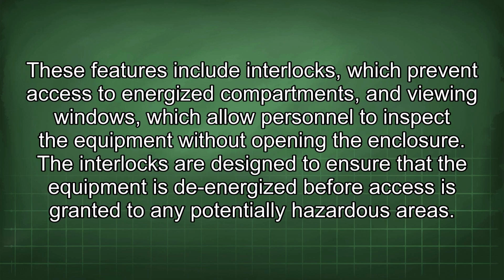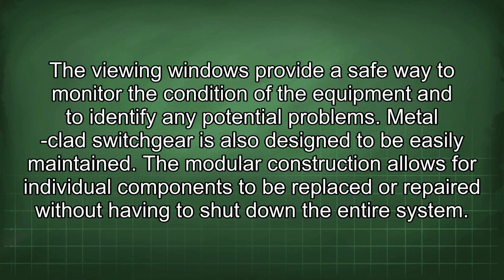These features include interlocks, which prevent access to energized compartments, and viewing windows, which allow personnel to inspect the equipment without opening the enclosure. The interlocks are designed to ensure that the equipment is de-energized before access is granted to any potentially hazardous areas. The viewing windows provide a safe way to monitor the condition of the equipment and to identify any potential problems. Metal-clad switchgear is also designed to be easily maintained.